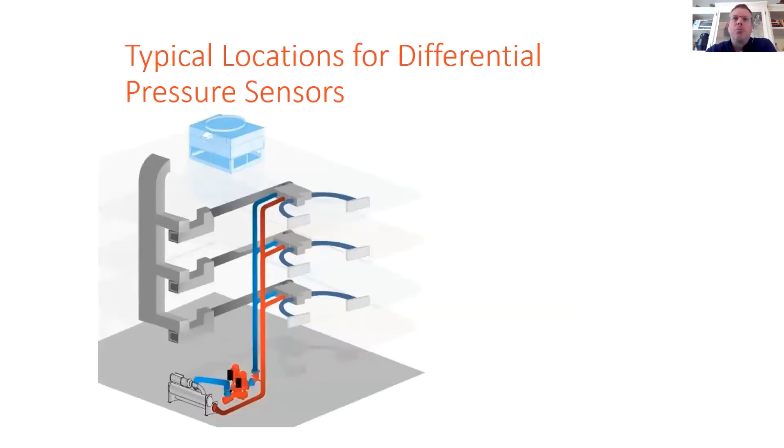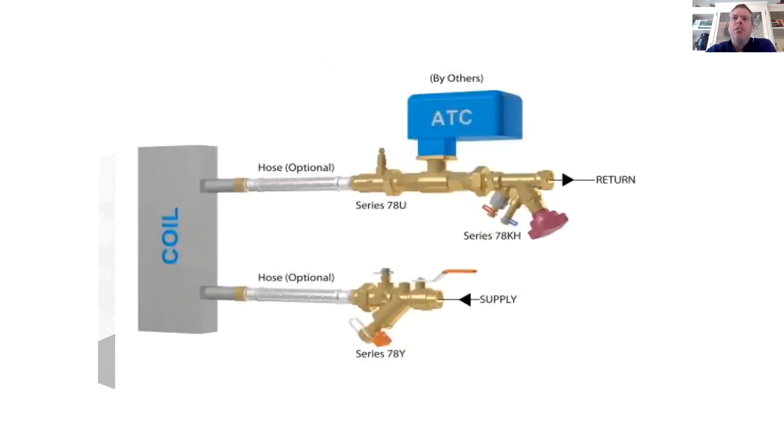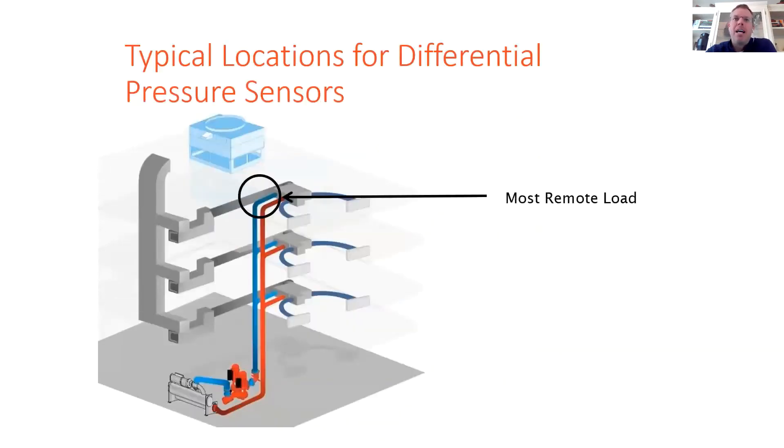The location of the differential pressure sensor is actually critical to the amount of energy that can be saved at the pump. The first and most ideal location is at the most remote load. So this is the load with the longest run of piping where the fluid is going to experience the most pressure drop before reaching the load, and the set point is typically the pressure drop needed to overcome the control valve, the strainer, the balancing valve, the coil, et cetera, and a short run of piping. This allows your minimum head set point to be low in comparison to the full flow head pressure set point and allows a great deal of pump turndown.